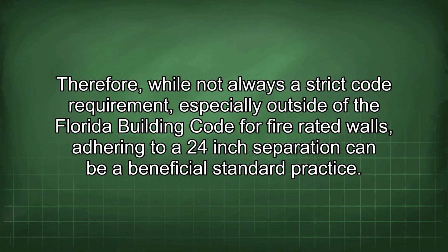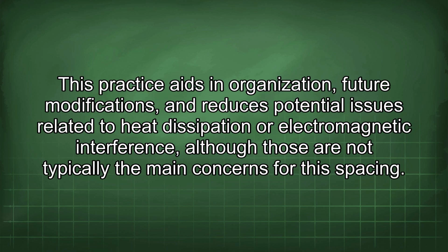Therefore, while not always a strict code requirement, especially outside of the Florida Building Code for fire-rated walls, adhering to a 24-inch separation can be a beneficial standard practice. This practice aids in organization, future modifications, and reduces potential issues related to heat dissipation or electromagnetic interference, although those are not typically the main concerns for this spacing.